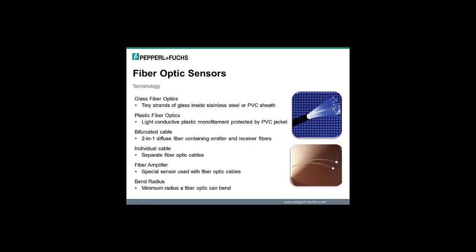Terminology used with fiber-optic sensors: glass fiber-optics are a type of fiber-optic cable with tiny strands of glass bundled together inside a stainless steel or PVC sheath, and can be used with visible red or infrared light sources. Plastic fiber-optics use a light conductive plastic monofilament material protected by a PVC jacket and are only used with visible red light sources. Bifurcated refers to a two-in-one diffused fiber cable containing both emitter and receiver fibers. Individual cable refers to separate fiber-optic cables used for both emitter and receiver. Fiber amplifier is a special sensor for use with fiber-optic cables that houses both emitter and receiver. Bend radius is the minimum radius a fiber-optic cable can bend without damage.